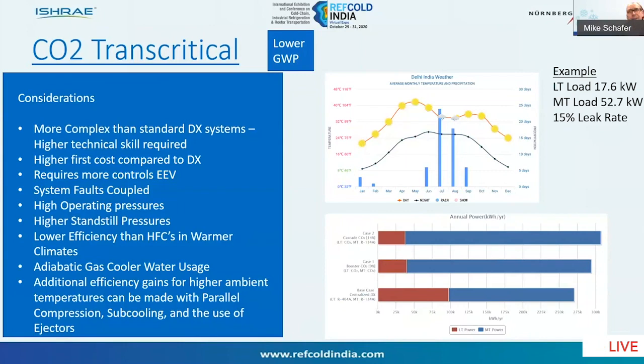So the simple example related to the TEWI calculation for Delhi. In this example, we used a small store load, roughly 17.6 kilowatts for the low temp and almost 53 kilowatts for the medium temp, and assuming a 15% leak rate. Looking at the average temperature distribution for Delhi, you can see that there's a number of months that the system would be operating transcritically.